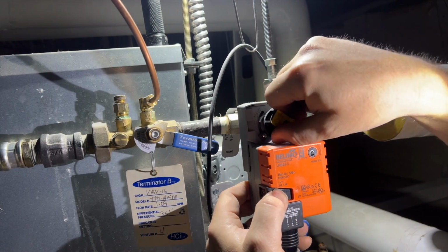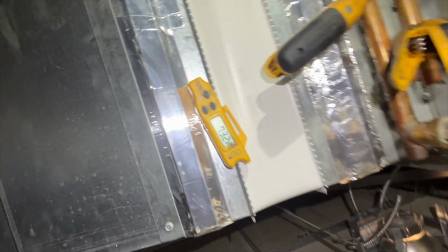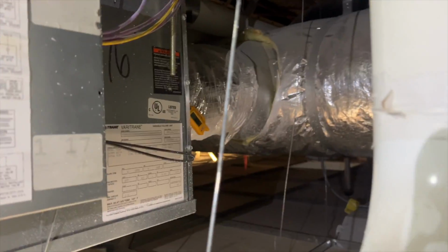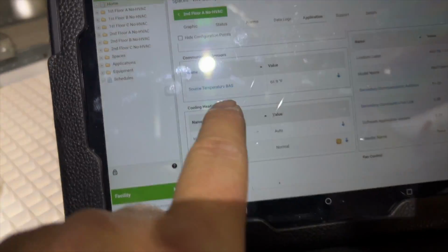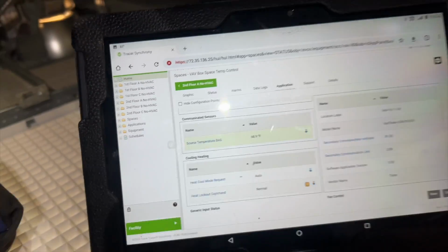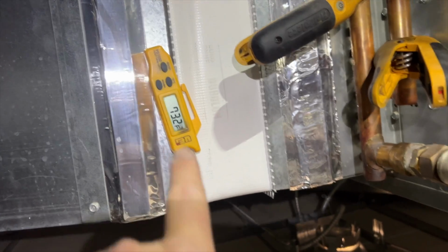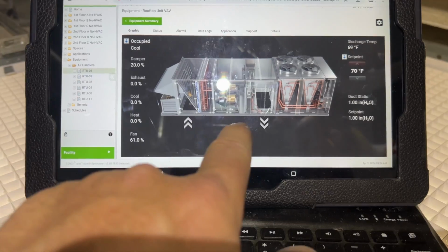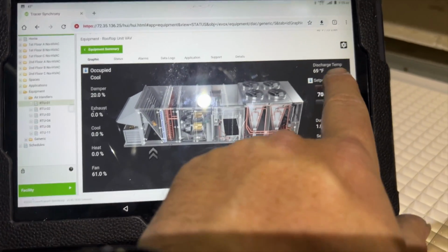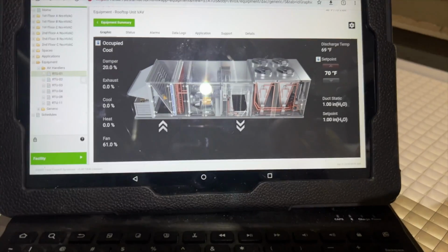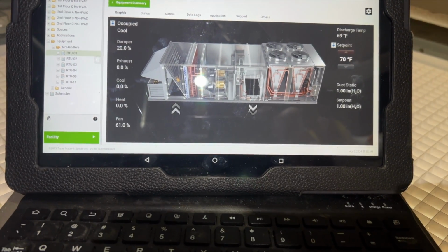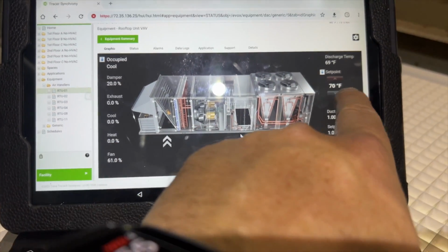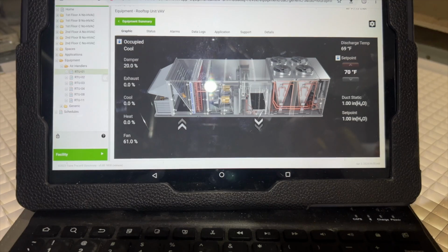My other clamp battery died, of course. That's open. So I got a thermometer over there. We got one right here, and we have one on the supply side. So it's reading about 70 degrees on unit supply. So according to this, our source temp is 68.9, so it's off by 2 degrees. Our discharge, 73.2. All right, so here's our IntelliPAC. Its discharge temperature is at 69 degrees. So we're not losing any of that temperature. Our set point is actually set to 70. So it's pretty much at set point.